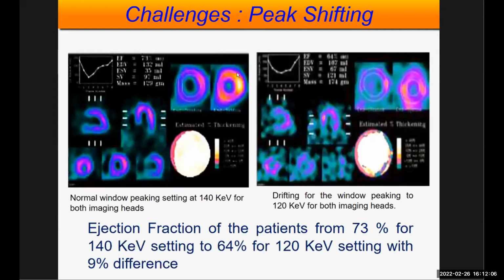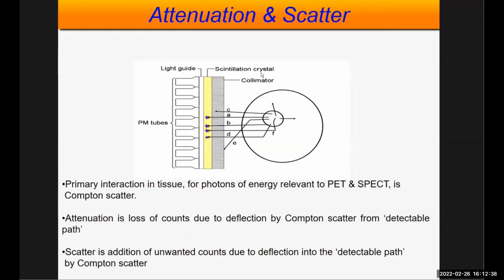Peak shifting also affects your image. You can see here the image when there is a shift in the peak, and the image acquired in the window at 140 keV. When we acquire the image at 120 keV, the ejection fraction is 64%, compared to the 140 keV image, where the ejection fraction is 73%, a difference of 9%.